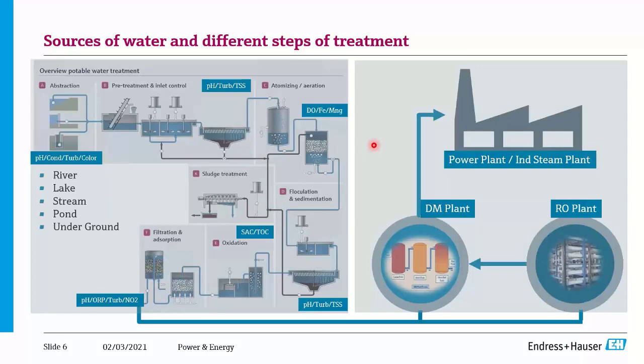How is water treated before feeding into the boiler? There are several treatment processes. For water from river, lake, stream, pond, or underground sources — the traditional treatment includes pre-treatment, aeration, flocculation and sedimentation, oxidation, filtration, and then it is pumped into the plant. When extracting water directly from the source, we need to know pH, conductivity, turbidity, and color — without measuring these basic four parameters, we cannot control the treatment at the inlet.